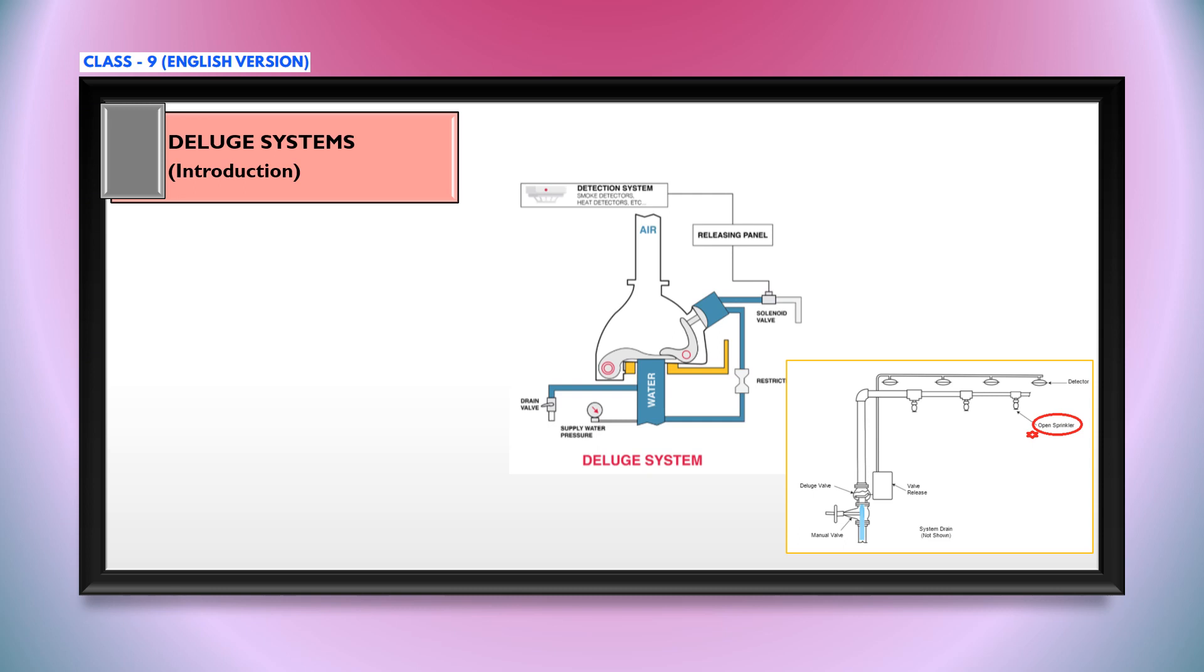A deluge system is a fixed fire protection system which totally floods an area with pressurized water through a system of piping and open nozzles or sprinklers. The system piping is empty until the deluge valve is activated by hydraulic, pneumatic, electric, or manual release systems.